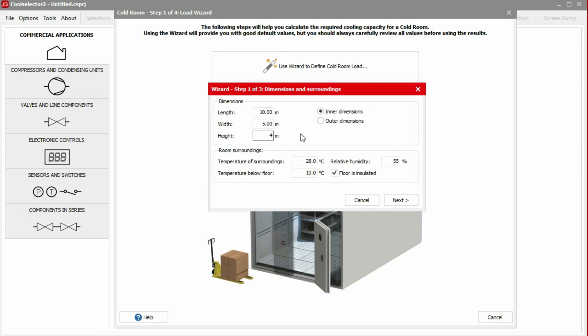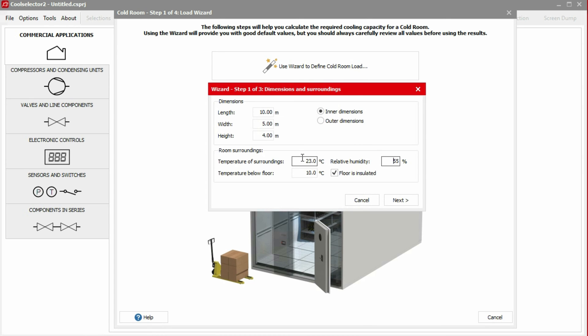We now need to define the conditions surrounding the cold room. This should be our maximum values but not values which happen rarely or only for a short duration. For this example, we'll use a surrounding temperature of 23 degrees Celsius, a relative humidity of 55% and a below floor temperature of 10 degrees Celsius. In this example, we'll also define the cold room as having an insulated floor. We then click next to continue.